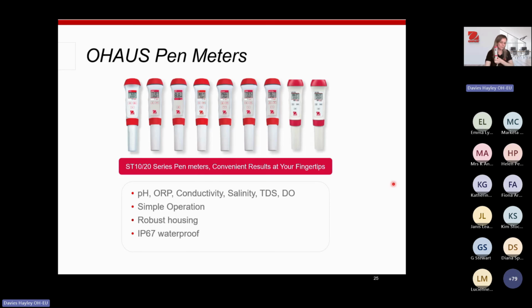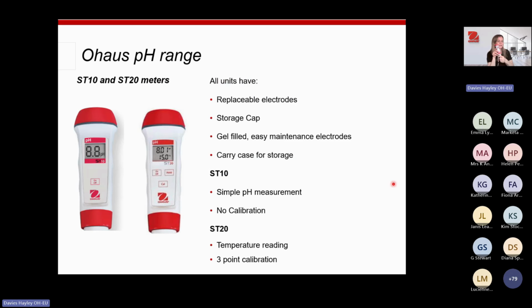The good thing about our electrodes here is that all of their units have a replaceable electrode. So the electrode here is the part that gets worn and will need to be replaced. And the good thing on these is they are fully replaceable. So you keep the measurement part of the electrode, and you just replace the electrode once it's been worn. So it's good from the sustainability aspect. You're not throwing a lot of the measurement electronics out into the landfill. You can just simply purchase the electrode, and it will be half the price of what the complete unit would have been.